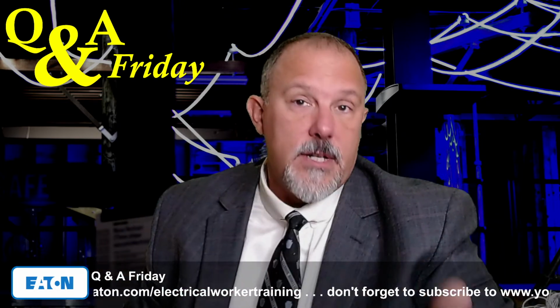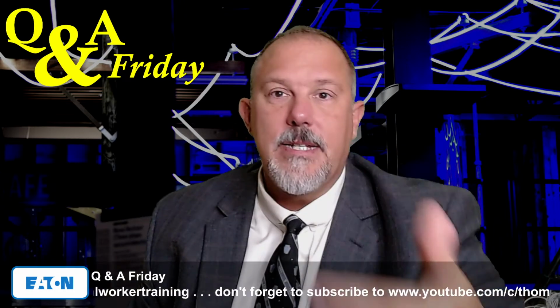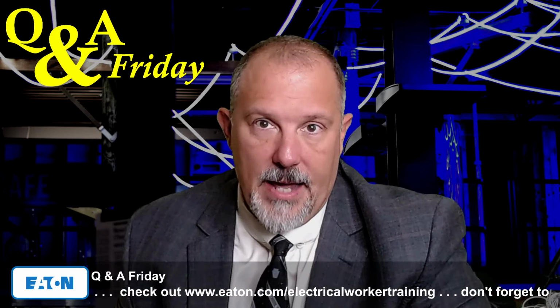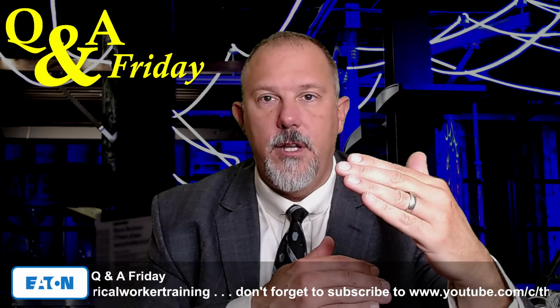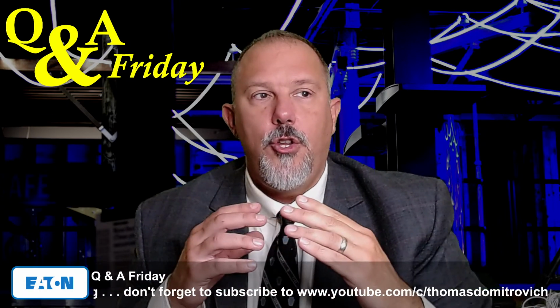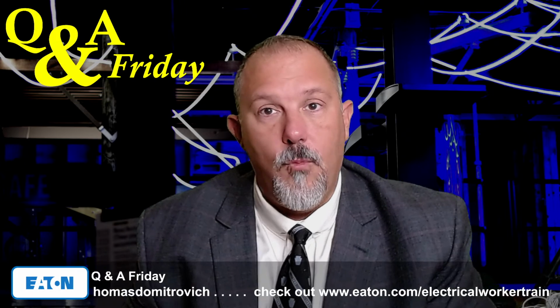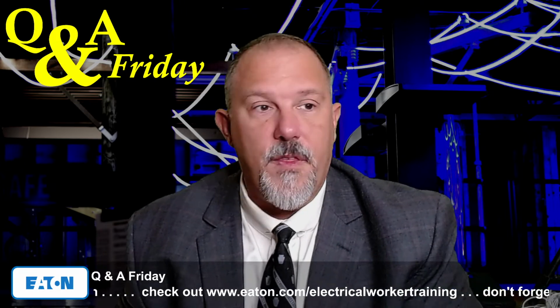And in addition to that, when you start with calculations, like for example, full load amps of a transformer, you're going to take the kVA divided by 3. It's going to be a whole number. It's going to be a nice even number. There's not going to be any decimal points. But in that same equation, you have divided by the square root of 3. If you take the 3-phase kVA and divide that by the square root of 3, now you have an equation within which there's another equation. You have what we would call a series of accuracy within. You have the accuracy of a calculation within the accuracy of another calculation.